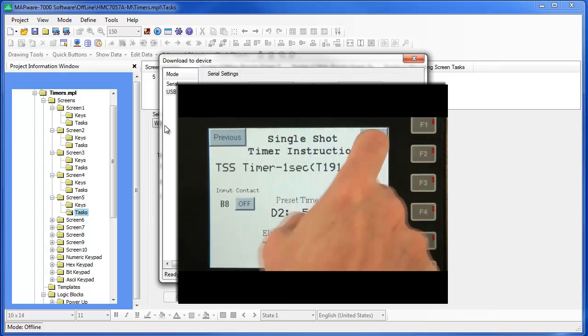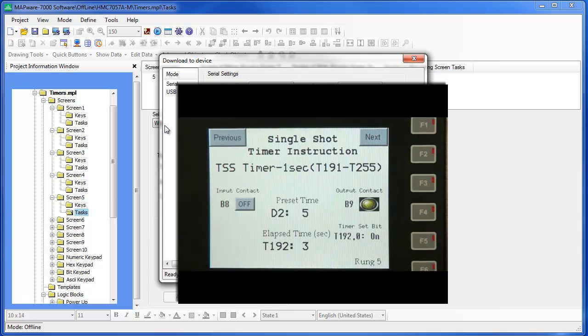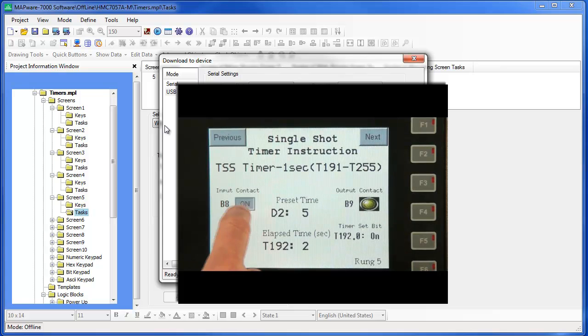Screen 5 displays a single shot 1 second timer configured to count to 5 seconds. When the B8 input contact is pressed, the contact turns on, starting the timer. Unlike the on timers, output contact B9 and the timer set bit immediately turn on as the timer continues the count. Note that B8 goes off as soon as the button is released since it is configured as a momentary switch. Although the input contact is now off, the timer continues to count for 5 seconds. While the timer is counting, switching the input contact on and off has no effect. When the preset value is reached, output contact B9 and the timer set bit go off and remain off until the timer is active again.